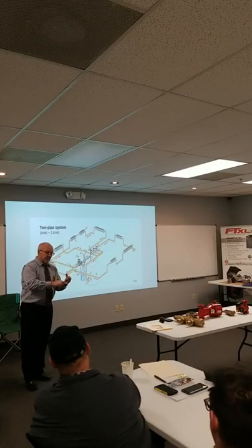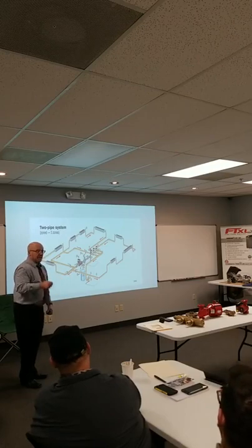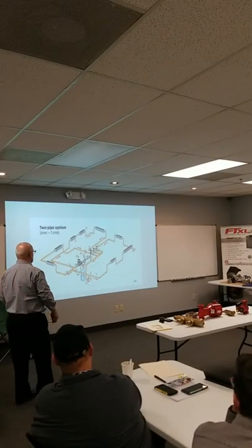So highest heat, lowest pressure. If you put the air separator on the suction side of the pump, guess what? On the outlet of the boiler, you're at the highest water temperature and you're at your lowest pressure. That's the best place to put it.